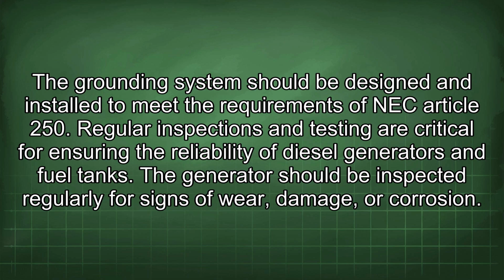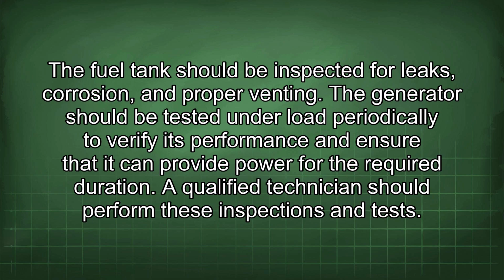Regular inspections and testing are critical for ensuring the reliability of diesel generators and fuel tanks. The generator should be inspected regularly for signs of wear, damage, or corrosion. The fuel tank should be inspected for leaks, corrosion, and proper venting. The generator should be tested under load periodically to verify its performance and ensure that it can provide power for the required duration. A qualified technician should perform these inspections and tests.